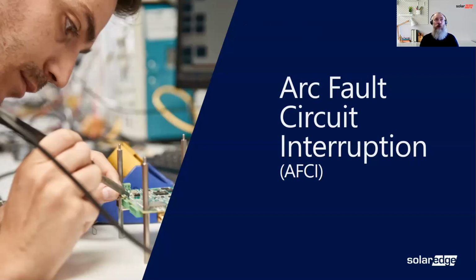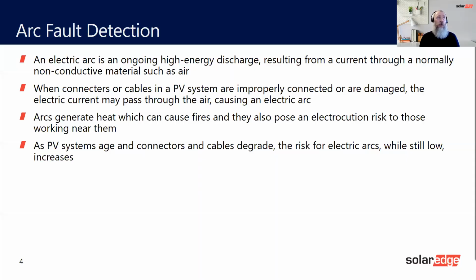So we'll just quickly go over arc fault circuit interruption first of all. Just a very brief explanation of it. I've already said, just to catch up, that basically it's the arc that can start the fire. It's the arc that raises the temperature, and that can also pose electrocution. So if you can remove the arc, and with the power optimizers, we can do that. We can simply turn down the power optimizers from 14 to 15 amps, say, down to 200 to 300 milliamps. We can reduce that arc.